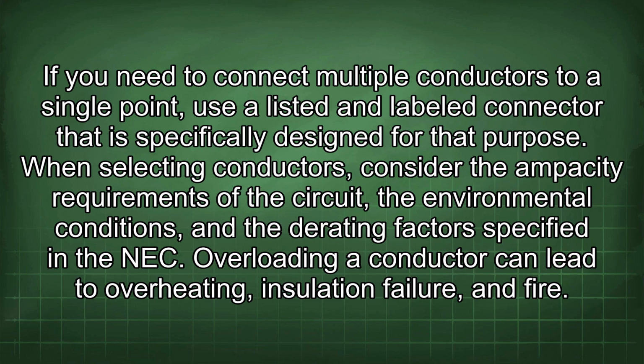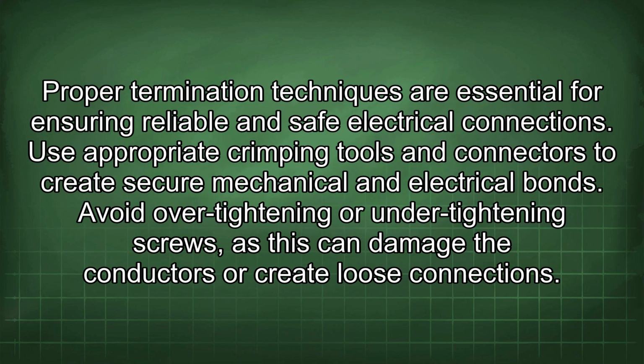Overloading a conductor can lead to overheating, insulation failure, and fire. Proper termination techniques are essential for ensuring reliable and safe electrical connections. Use appropriate crimping tools and connectors to create secure mechanical and electrical bonds. Avoid over-tightening or under-tightening screws, as this can damage the conductors or create loose connections.